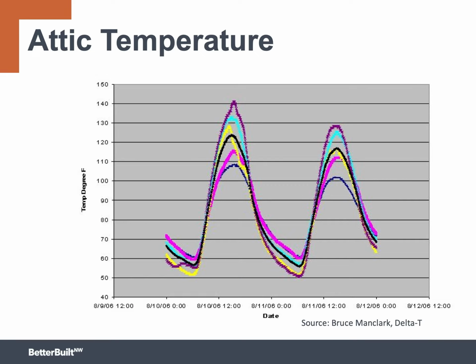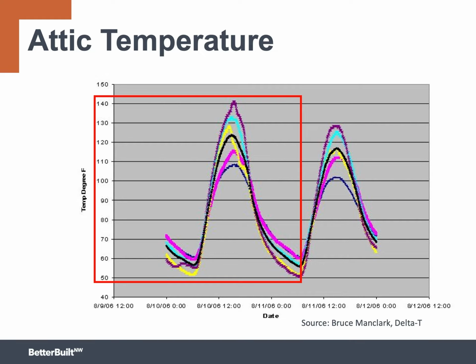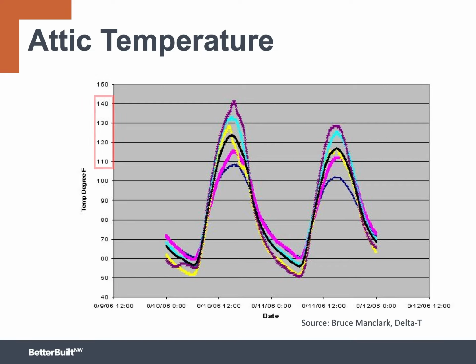Let's look at one critical issue on the cooling side. This chart shows the daily temperature swings for 6 attics in August. There are only 2 days represented here. The smallest temperature swing is 50 degrees and the highest is 90 degrees. The temperature peaks out anywhere between 110 and 140 degrees. That's the temperature in the attic that these ducts are exposed to. And a similar thing happens in the winter, when the attic air is pretty close to the same temperature as the backyard. Attics are hot in summer and they're cold in winter, and it's just not the place where you want to put ducts.